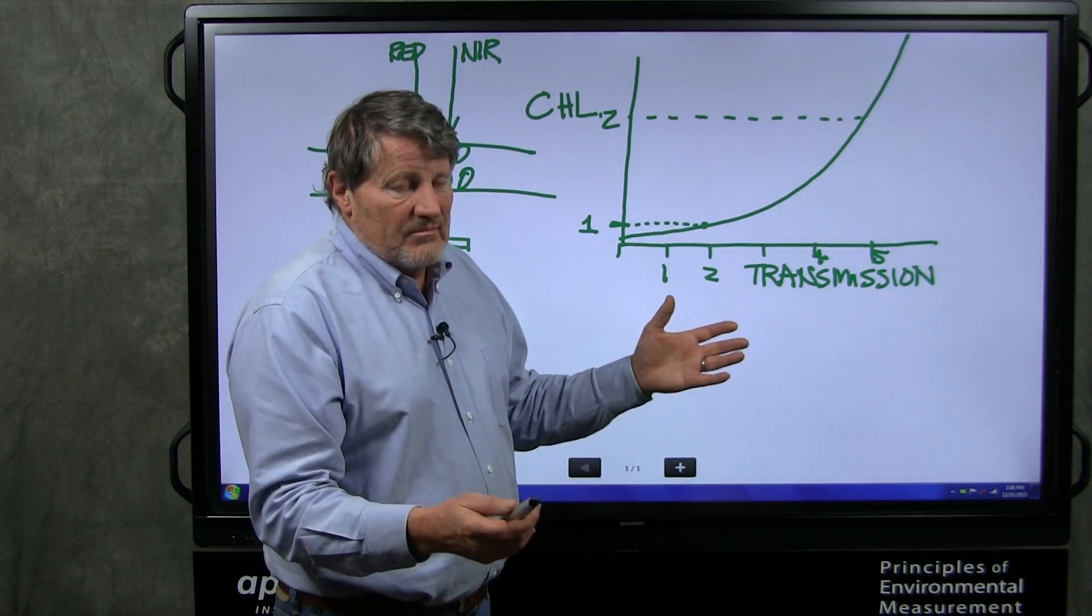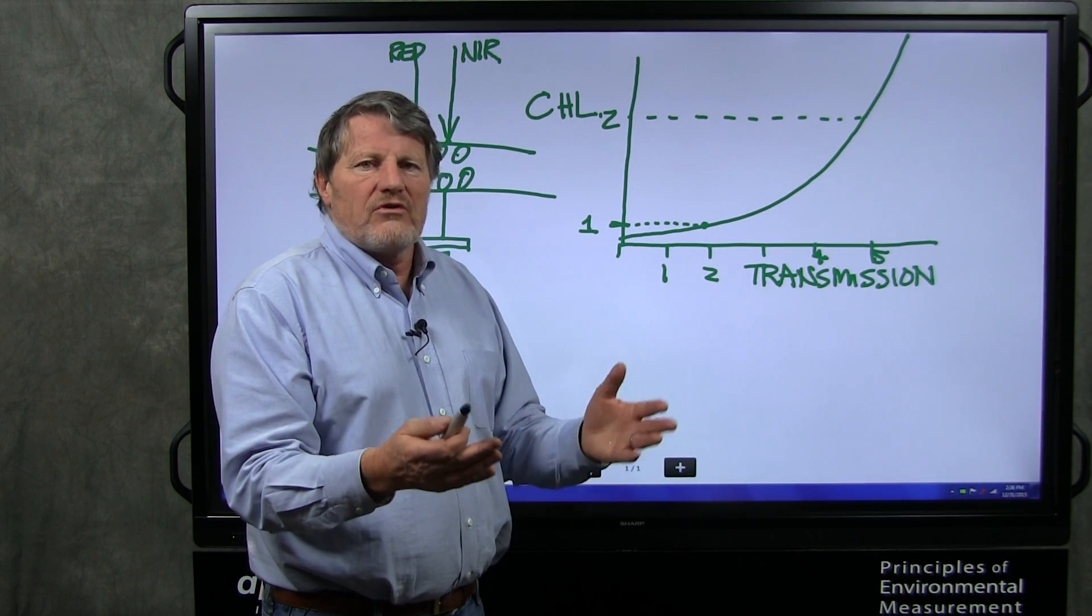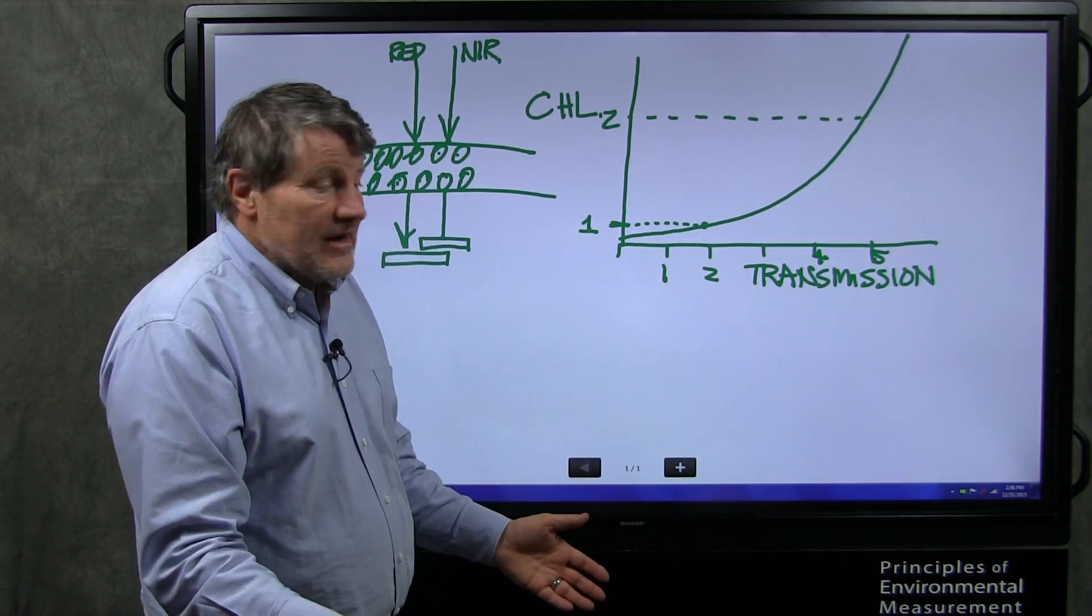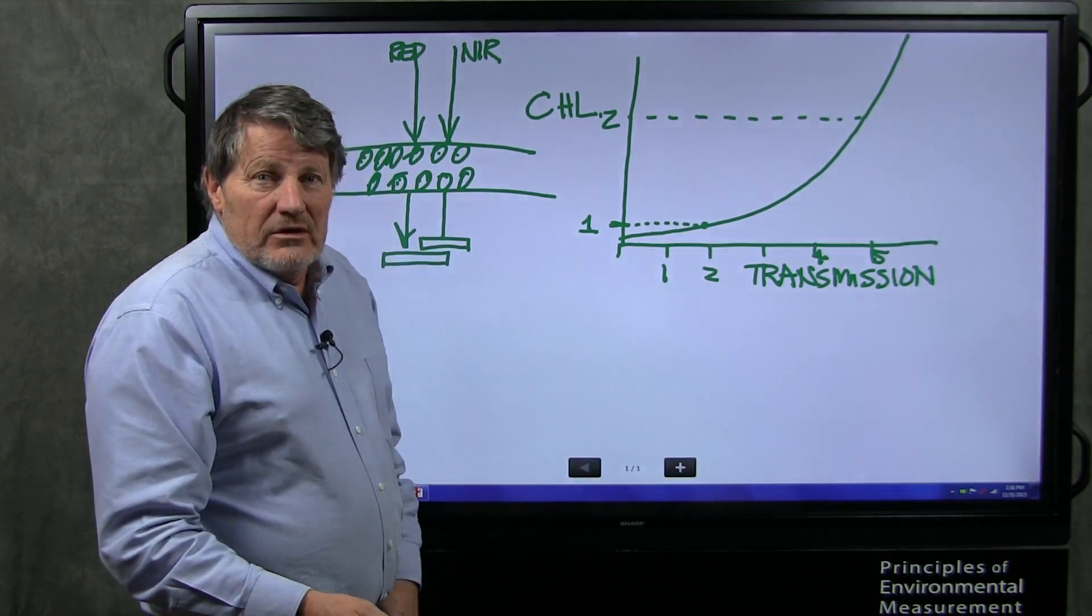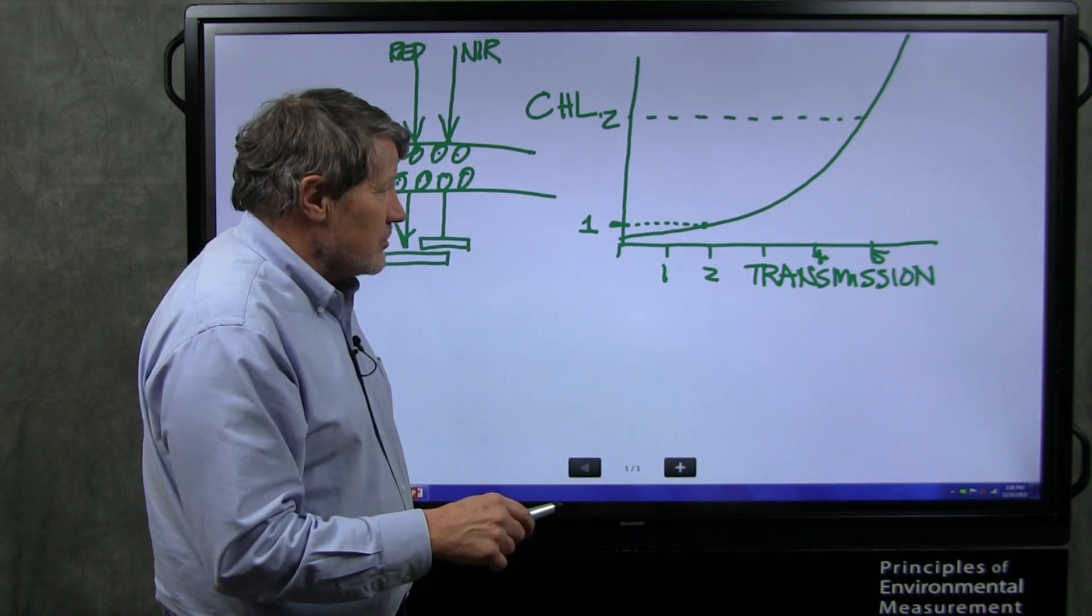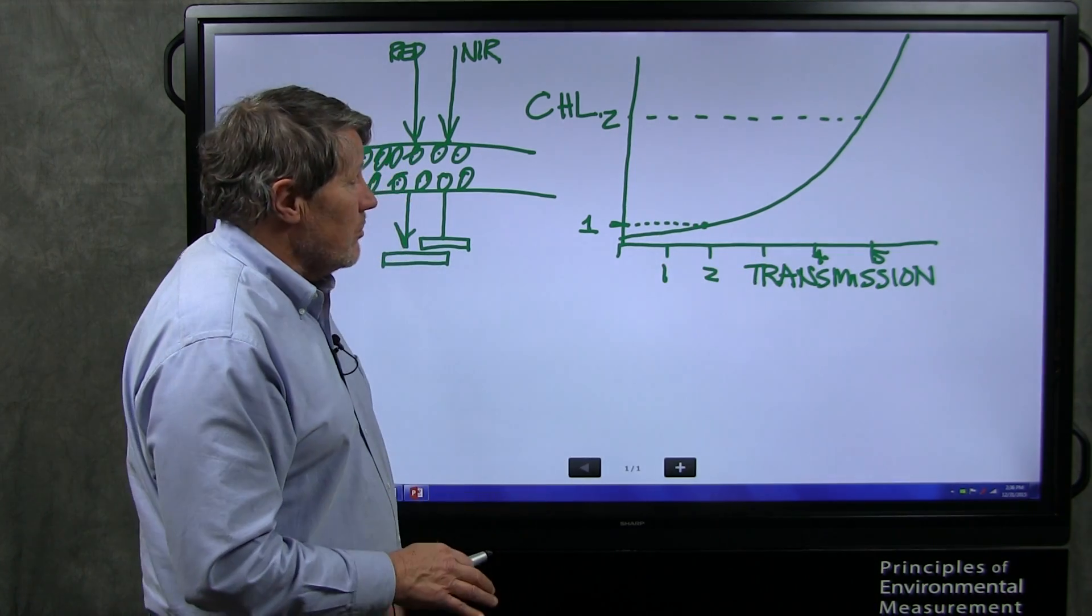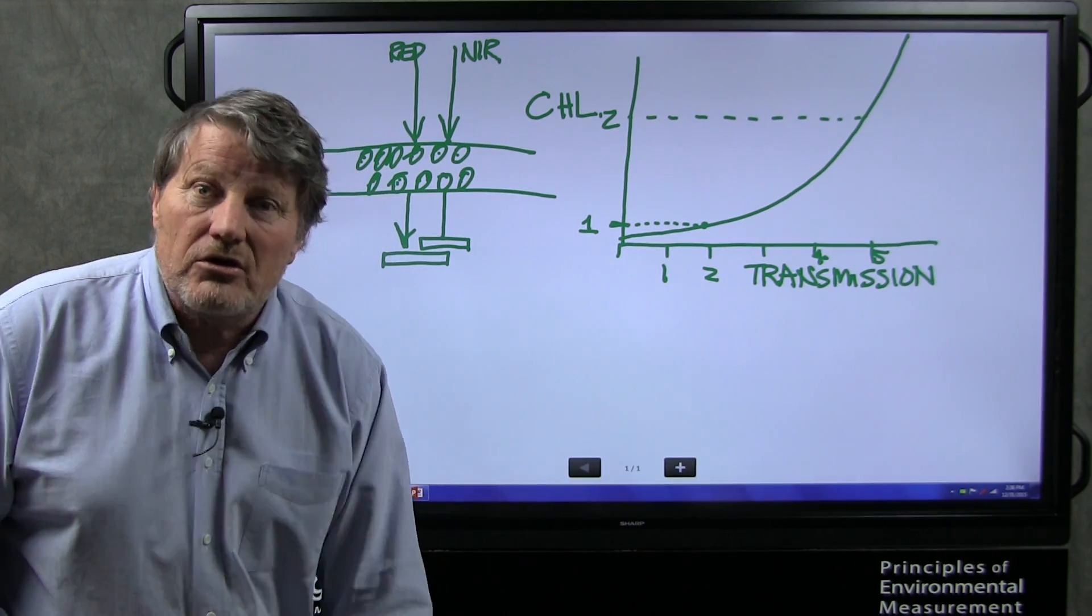This has led to lots of problems. People write papers and they say the SPAD number went from two to four, therefore my chlorophyll doubled. And that is wrong. The chlorophyll did not double. This index doubled. So the SPAD Minolta meter that reads in SPAD units only gives an index that's non-linearly related to chlorophyll. The OptiSciences meter also gives an index that's non-linearly related to chlorophyll.